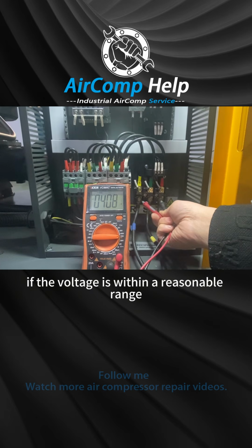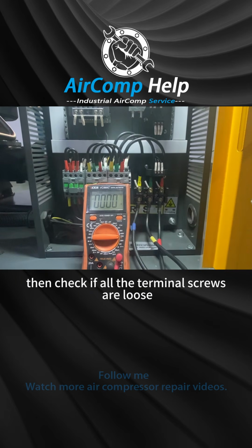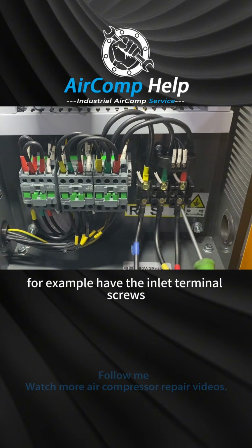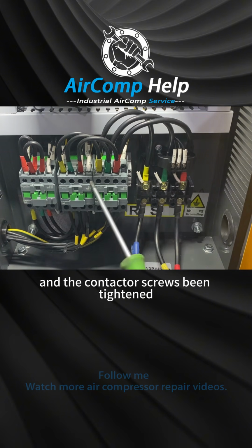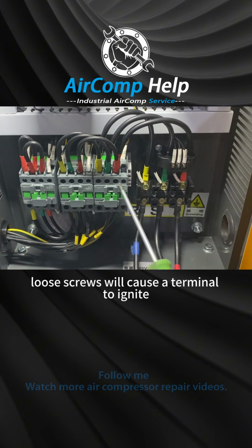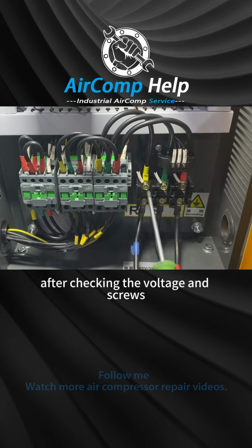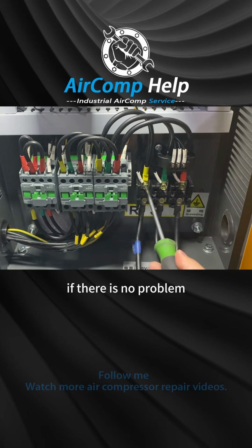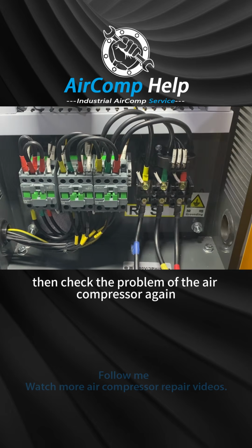If the voltage is within a reasonable range, then check if all the terminal screws are loose. For example, have the inlet terminal screws and the contactor screws been tightened? Loose screws will cause the terminals to ignite, so it will exceed the current. After checking the voltage and screws, if there is no problem, then check the problem of the air compressor again.